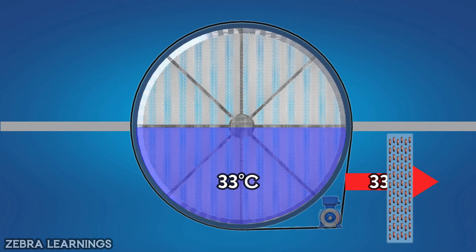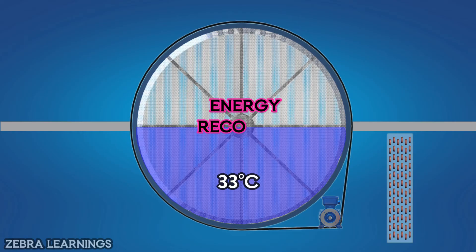The air exiting the thermal wheel is further cooled as it travels through the cooling coil. Before traveling through the cooling coil, the temperature of the air is reduced by the thermal wheel. That's why we call the thermal wheel the energy recovery wheel.